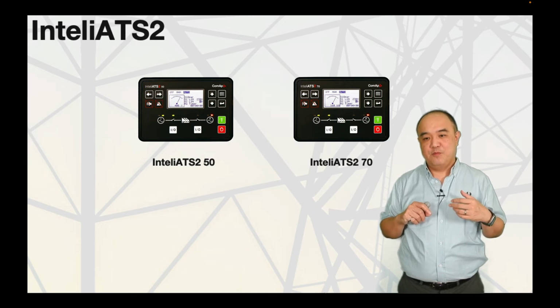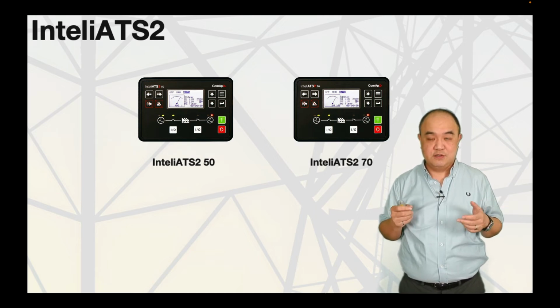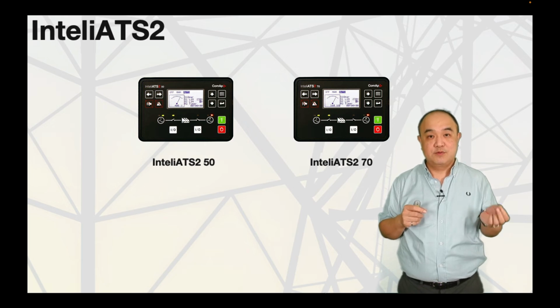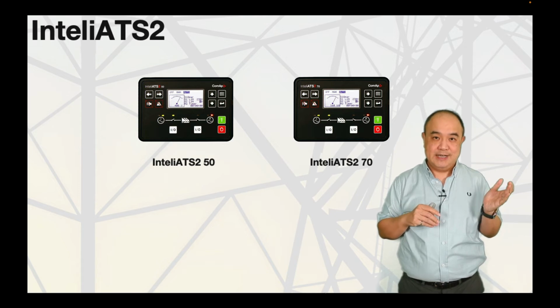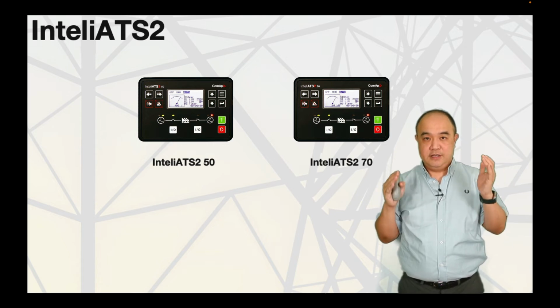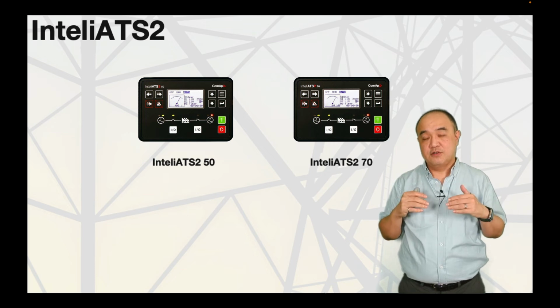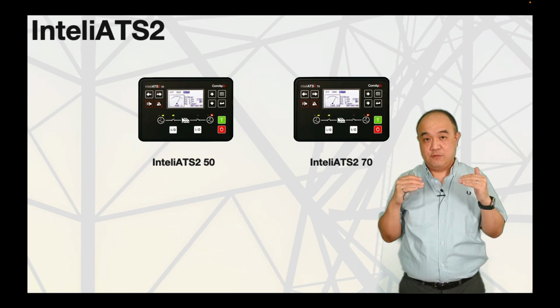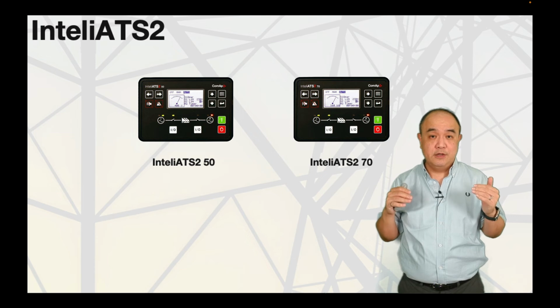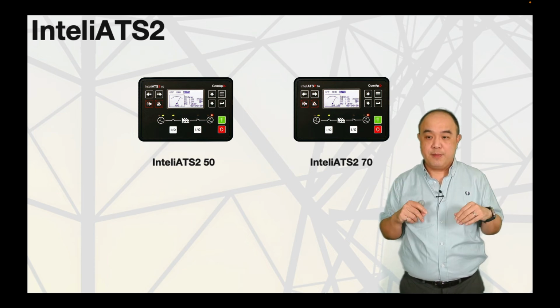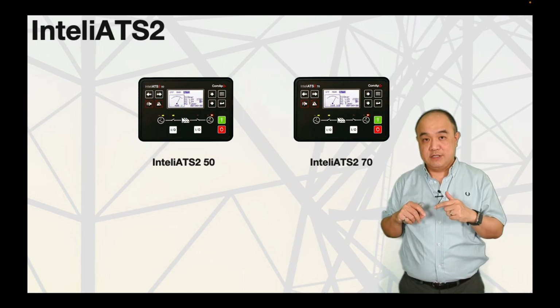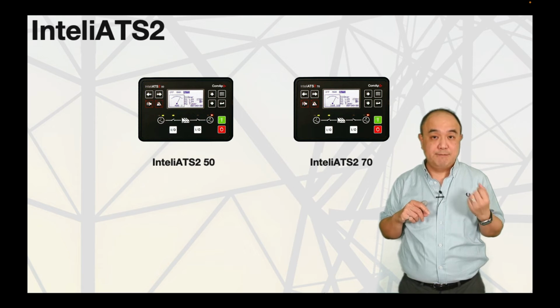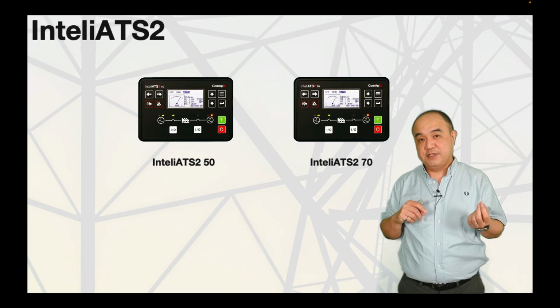So what are the new features of this series? Of course, programming is now with USB. Both versions support, of course, genset and mains ATS switchover control. They also support two mains switchover much better than the old series. And for the 70 model, you also have a built-in PLC you can use. The 50 has no PLC. The 70 has a PLC you can use.